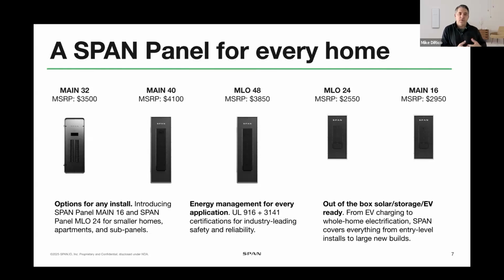Over the course of a few years, we took that feedback and said, okay, the market has asked, and we're going to deliver. What the market asked for was panels more right-sized for different applications. So now we have our main 40 - SPAN panel main 40. Main means it has a main circuit breaker: a 200 amp main breaker integral to the panel, and 40 branch breaker circuits.